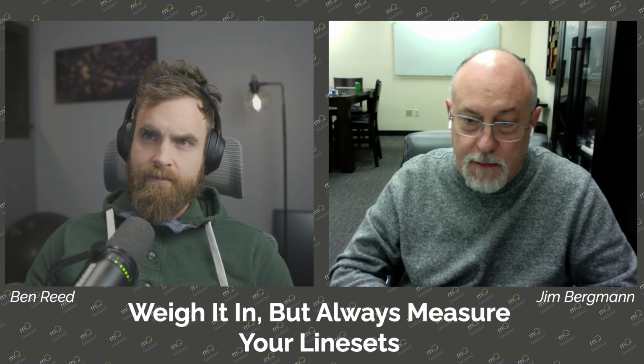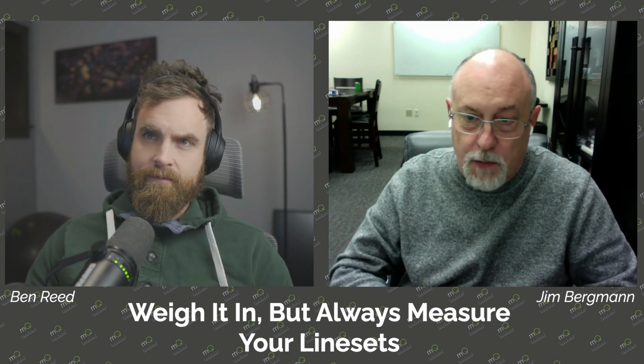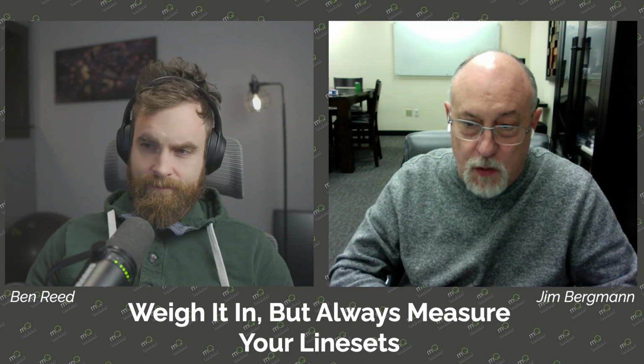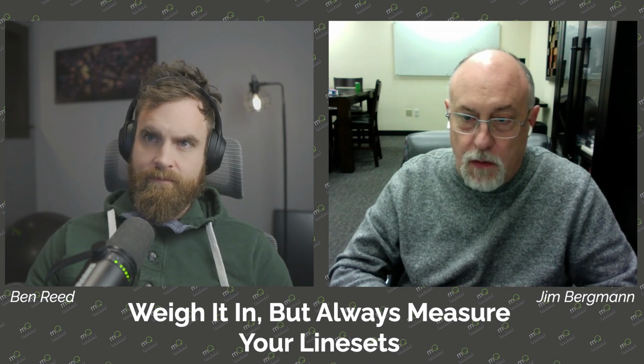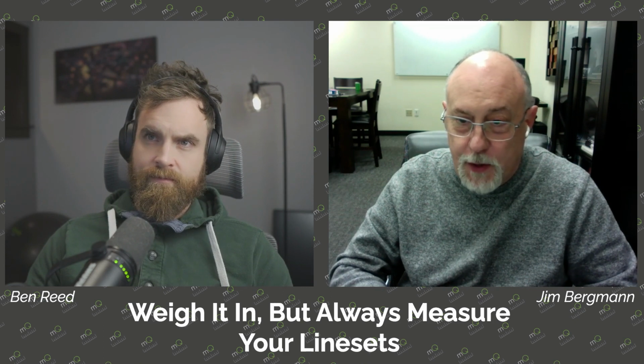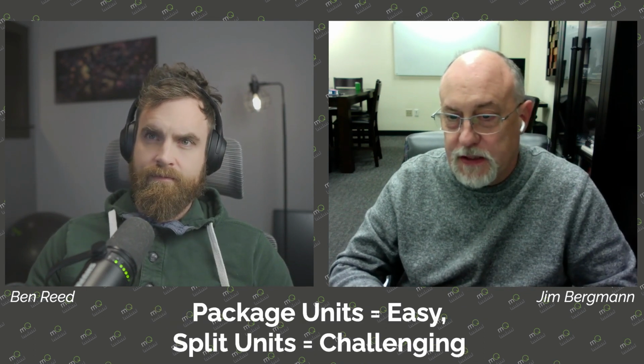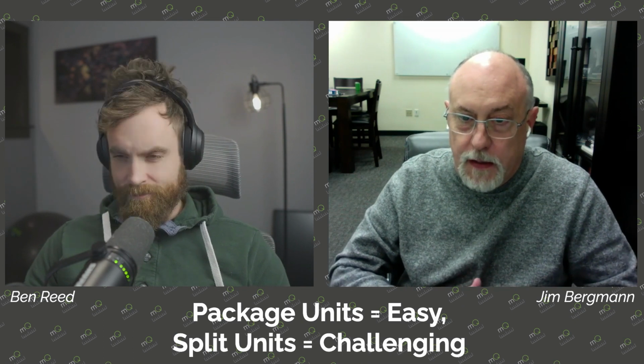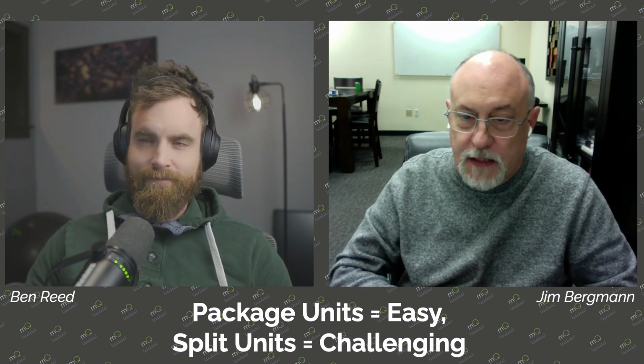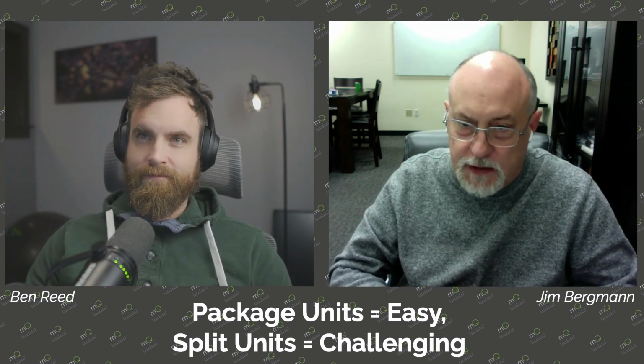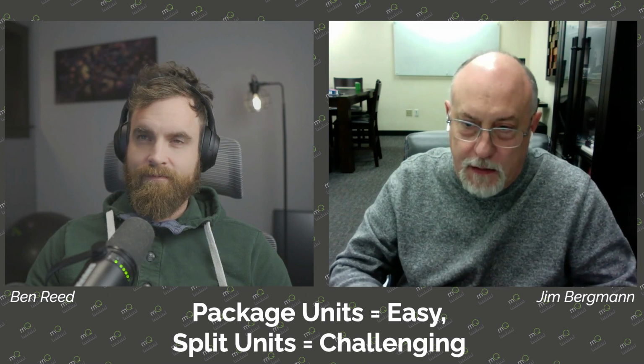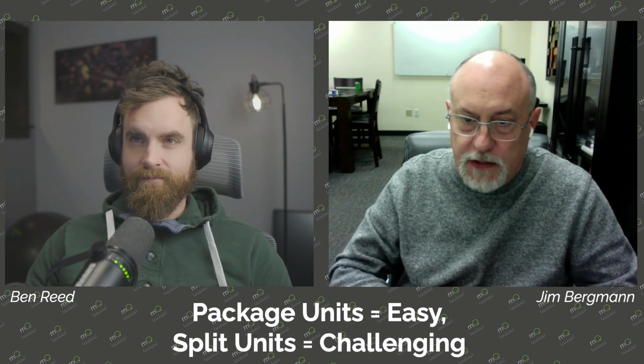Because people don't think about this too. You could pair up a system with a 4-ton coil or a 5-ton coil. We have to know by the configuration how much refrigerant the evaporator coil holds, because different coils hold different amounts of refrigerant. So line set length isn't the only variable. If these are package units, this is really easy because a package unit comes charged from the factory. And worst case, like you have a Schrader core leak, you recover the existing refrigerant and just weigh back in the right amount. Pretty simple.